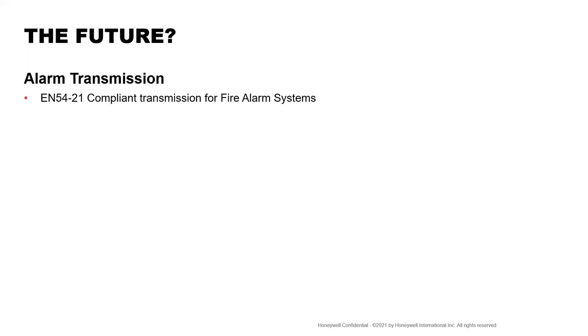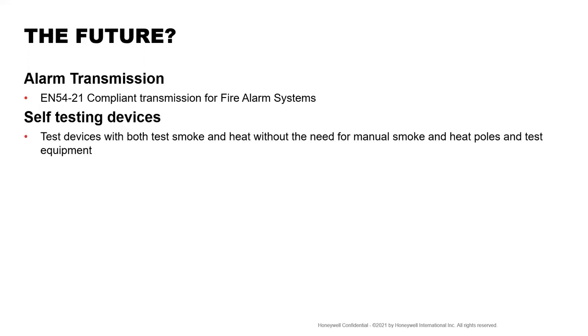So EN54 part 21 compliant transmission for alarm systems, as we just spoke, self-testing devices. The test devices both test smoke and heat without the need for manual smoke and heat poles. That's going to be massive, because the difference between walking in and disrupting an office to get people to move out of the way so you can get on a ladder and check the smoke detector, you can do it all now with absolutely zero disruption for that particular building. That's huge from an end user's perspective.